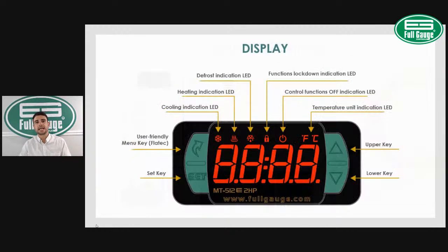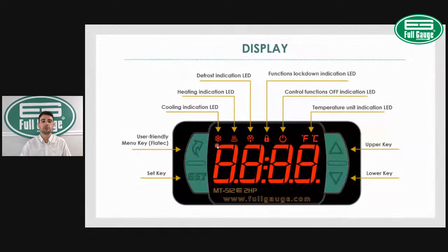So let us understand the display of the MT512. That's one of the beauties about digital controls, that you have instant feedback on your controller about the current state of the system. For example, on the top of our screen in here, we have indication LED icons. We have one that indicates the cooling, whenever the cooling system is on or off. This controller has the capability of working under heating mode. If the controller is set for heating, the heating icon would be lit in here. We also have a defrost indication LED. Whenever the controller enters defrost, this defrost indication LED will be lit.